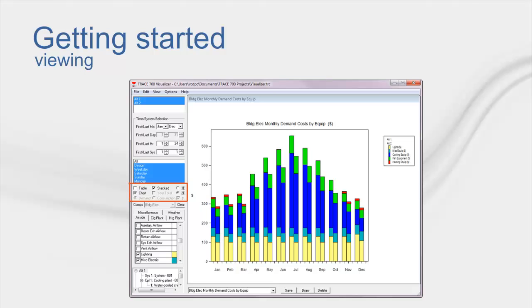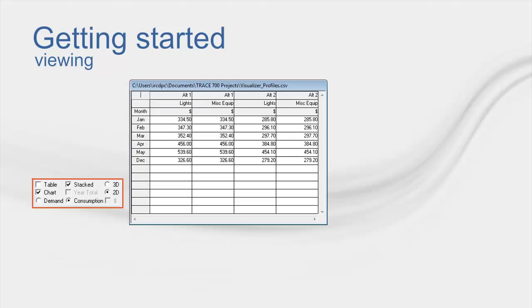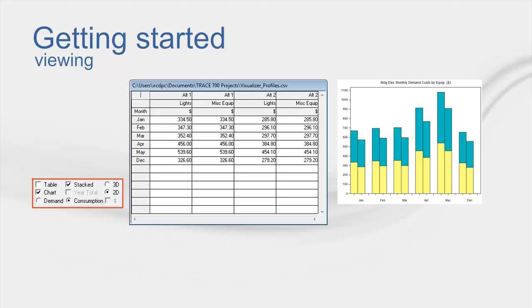The next section allows you to change the way you're looking at the displayed data. You can view the information in a table, or graphically, or both. You can also have the information stack upon each other so that you can get totals to compare against alternatives. Lastly, you can change whether you're looking at energy demand or energy consumption. This last part is particularly important because demand information is hourly, while consumption numbers are reported in monthly values.